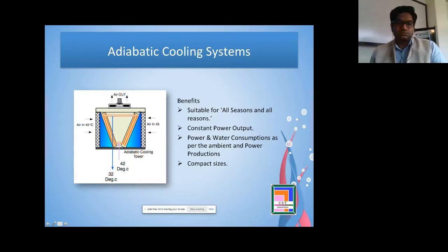So we have to change the metallurgy of the cooling tower, because the expected life of the cooling tower is a minimum of 10 to 15 years, and because of the environmental conditions, it should not affect or erode the fins. And there is a constant power output, because we don't have to derate the power plant and reduce the steam. Power and water consumption are as per the ambient and power production, and this is a system which works 8760 hours without any disturbance, because the whole system is automated with the VFDs and logic controls and everything, and this is compact in size.